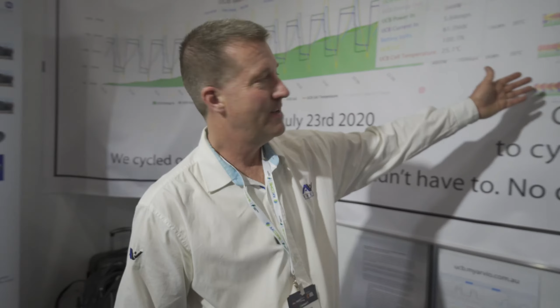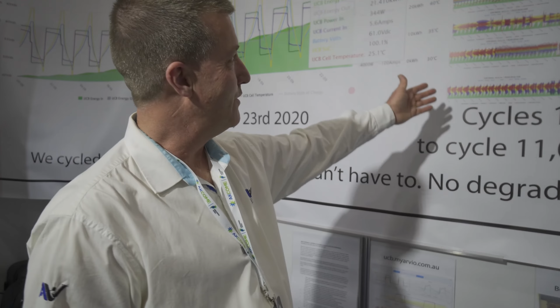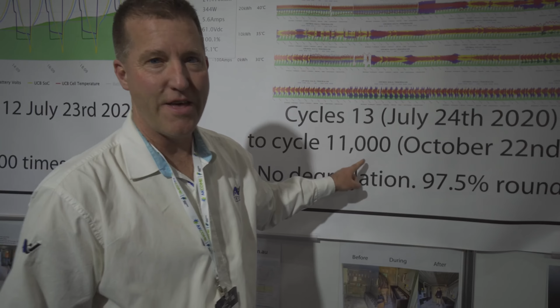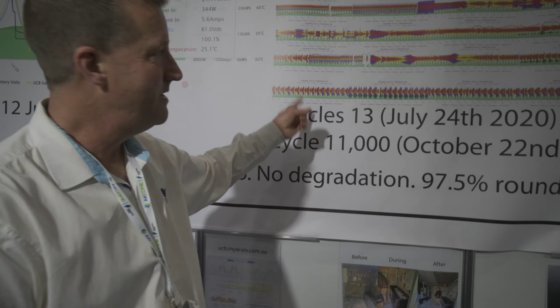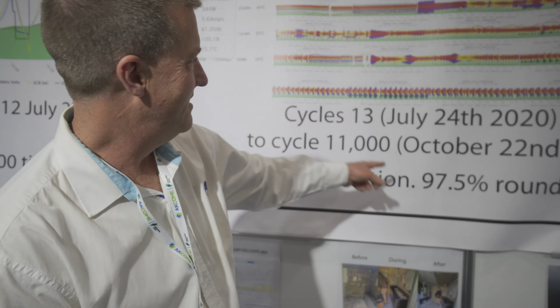Have a look, so this is actually the real cycles right here, cycles 13 through to cycle 11,000. Now if you do the calculations, that works out to 28 years, so if you want a battery that lasts 28 years, well we just cycled it at 28 years, at 1C, which means 1 hour up, 1 hour down, which is actually quite hard on a battery normally. This is every single real cycle, the little green triangles here are the days.